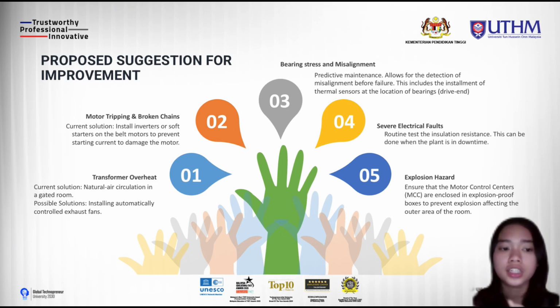So for the proposed suggestions for those 5 points, for the transformer heat, because there is already natural air circulation in the gated room, a possible solution is to install automatically controlled exhaust fans which turn on at a specific temperature threshold to suck out the heat. The second is motor tripping and broken chains, and a solution for this is to install inverters or soft starters on belt motors to prevent starting currents from damaging the motor.